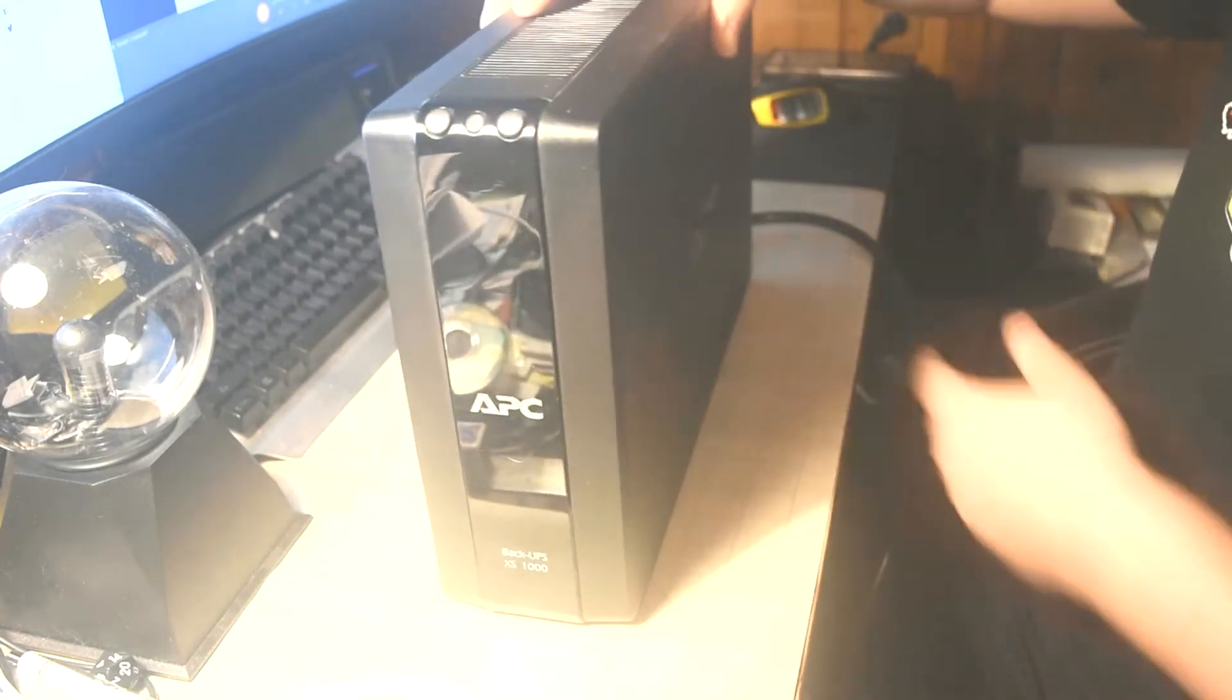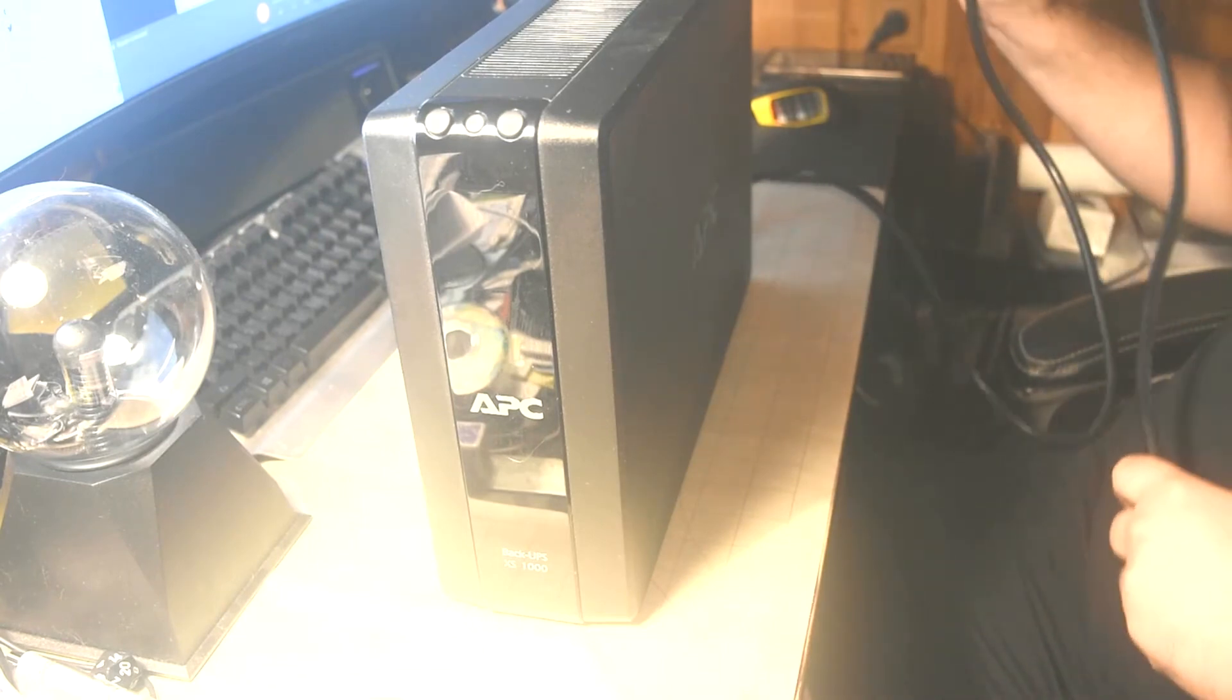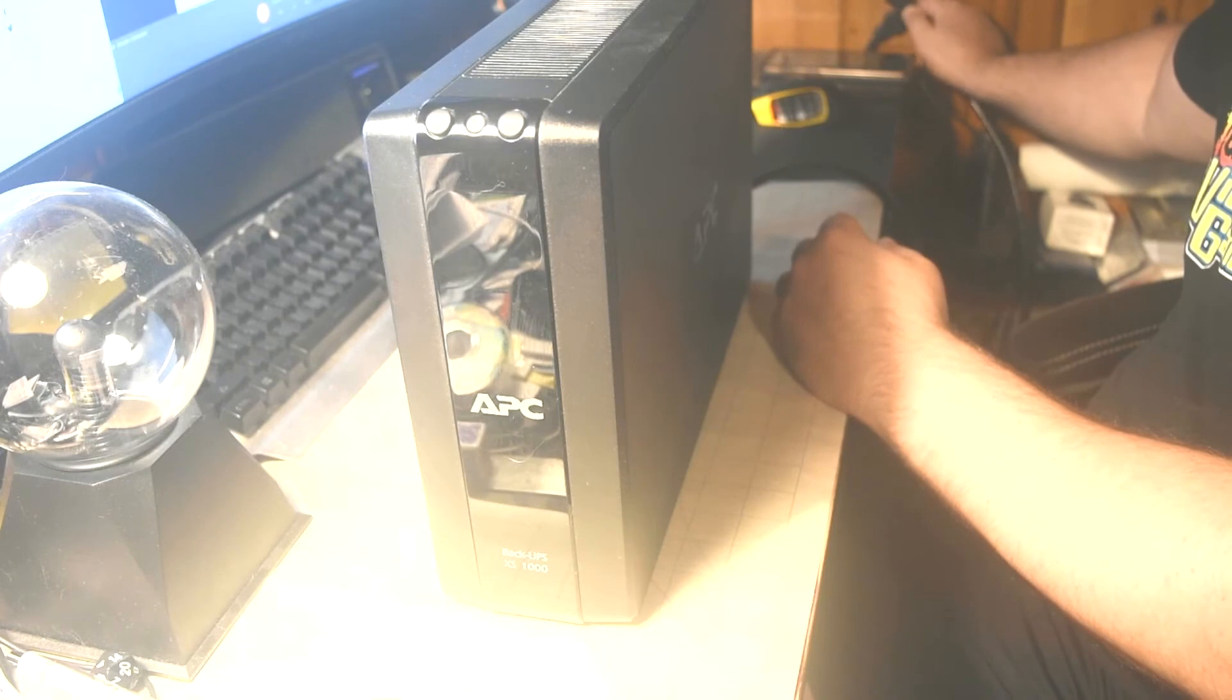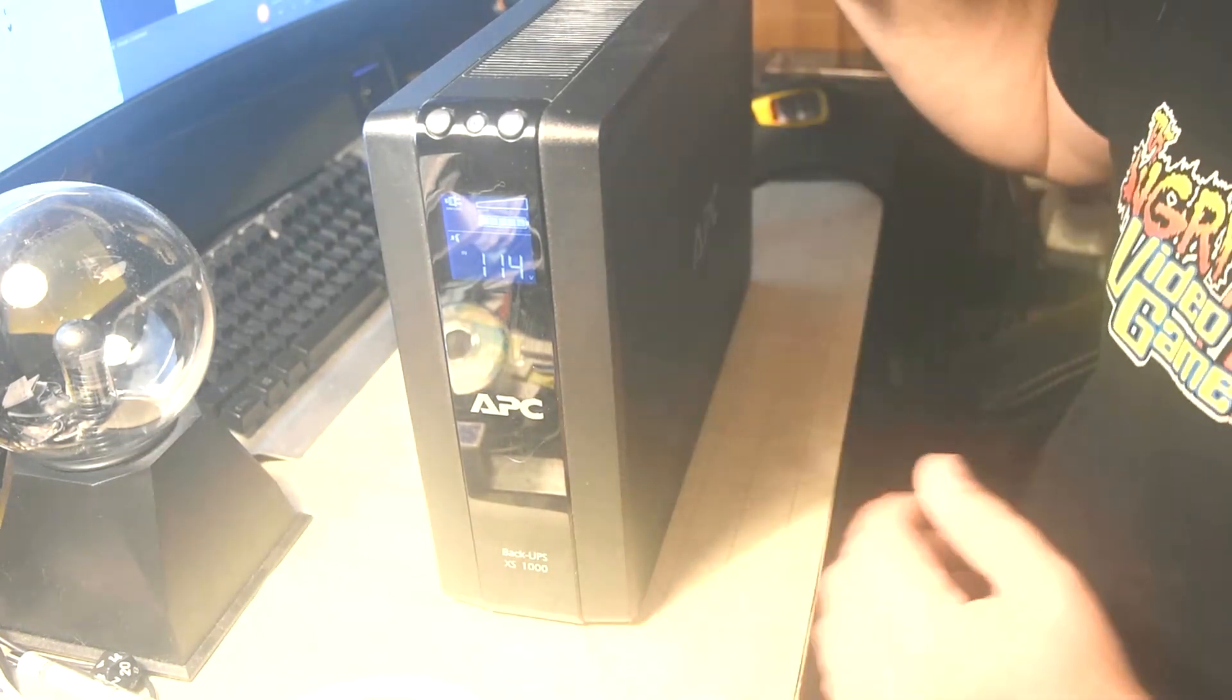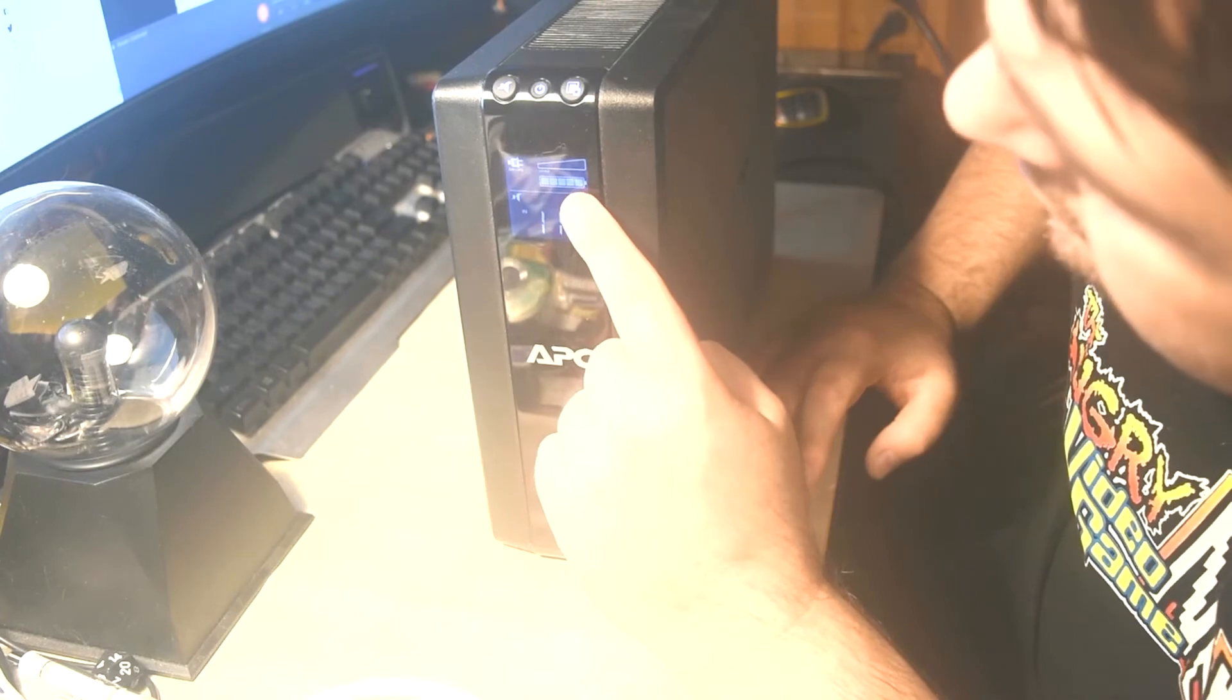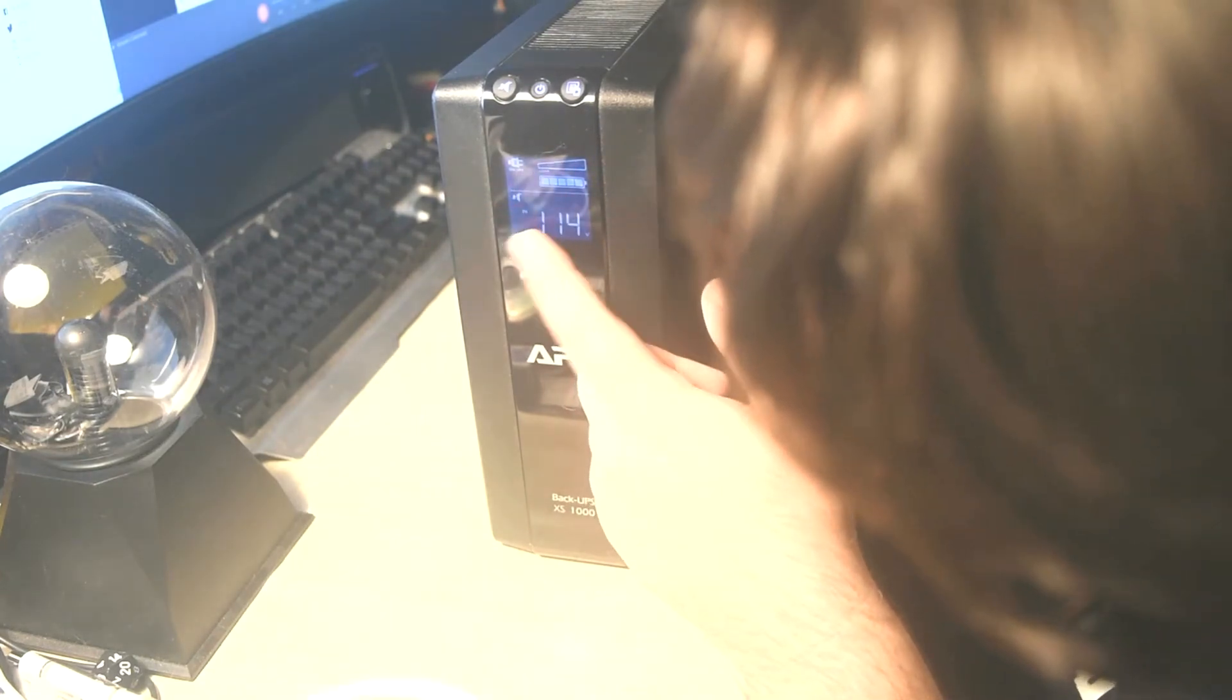We have successfully changed the batteries on an APC Back UPS XS1000 power supply. I'm going to plug this in now. Seems to power on perfectly. You see the display light. The battery meter is showing it's fully charged.